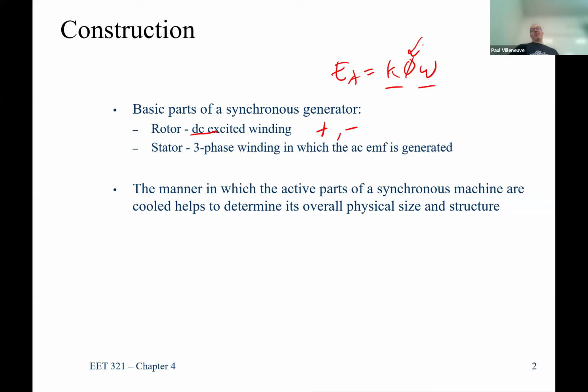Ideally, you would keep going up to higher and higher voltages. And I'm not exactly sure why people stop at 25,000 volts. I mean, there's nothing saying you can't run a generator at 138 kV. It just might be the physical spacing, because you can arc across things so easily. It just might be one of those things that it's physically impractical to design a generator that can run at that higher voltage. So the biggest generator voltage I've ever seen is 25,000 volts. But again, that's 1500 MVA, almost 50,000 amps. It would be a much cheaper generator if you could run that at 138 kV or, even better, 345. You could get your cables quite a bit smaller.